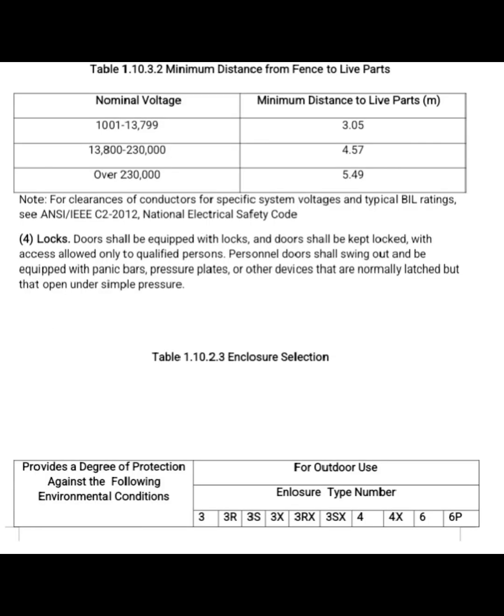Walls and roof must be built from materials that can resist fire for at least 3 hours, and floors must be made of strong material and at least 100 mm thick. Table 1.10.3.2 Minimum distance from fence to live parts. Nominal voltage 1001 to 13,799: minimum distance to live parts 3.05. 13,800 to 230,000: minimum distance to live parts 4.57. Over 230,000: 5.49.